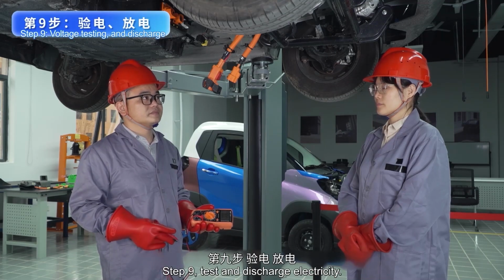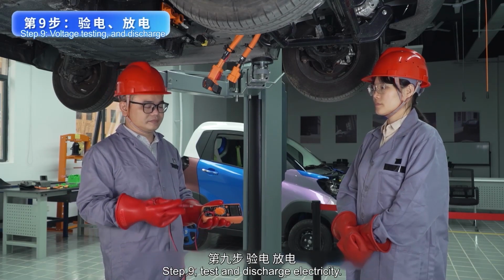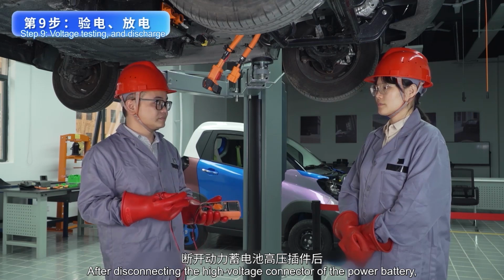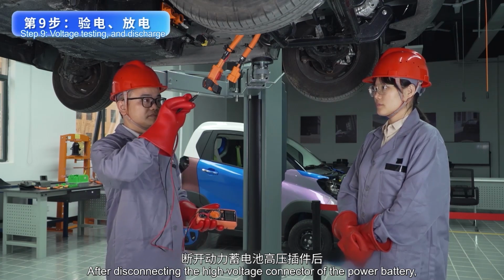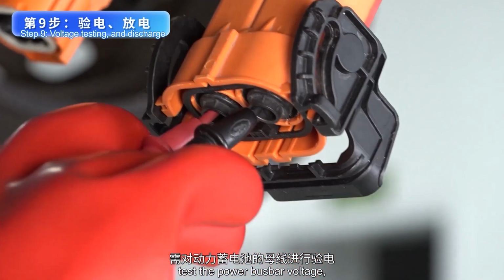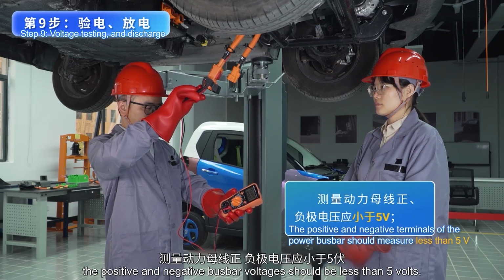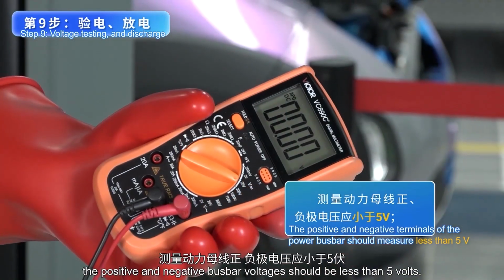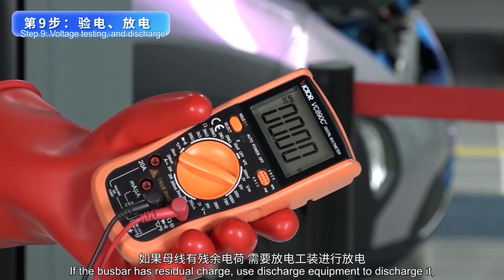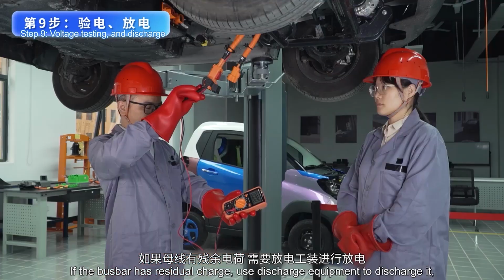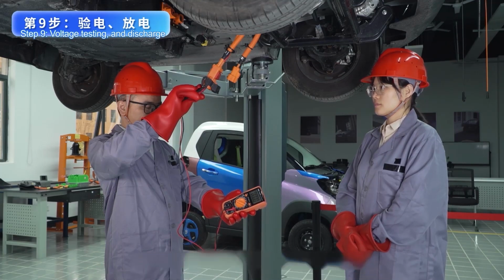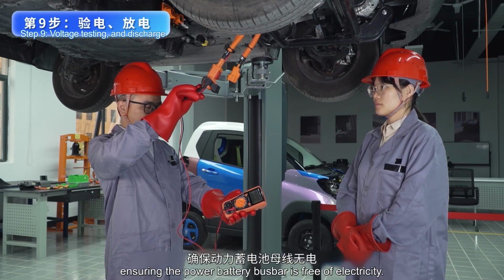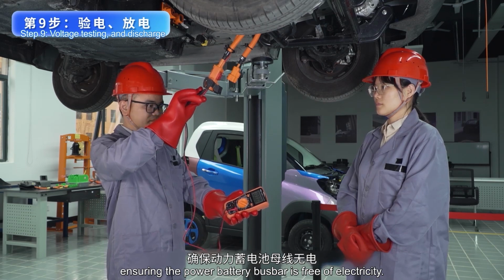Step 9. Test and discharge electricity. After disconnecting the high voltage connector of the power battery, test the power busbar voltage. The positive and negative busbar voltages should be less than 5 volts. If the busbar has residual charge, use discharge equipment to discharge it, ensuring the power battery busbar is free of electricity.